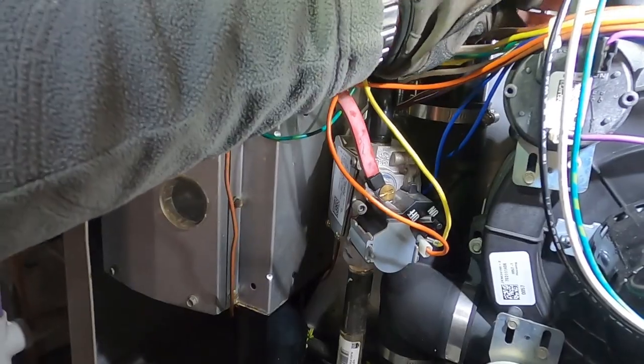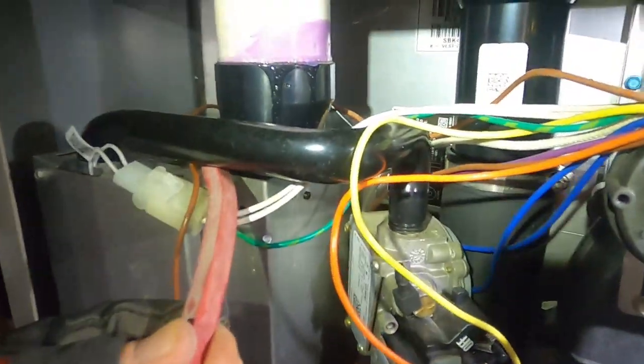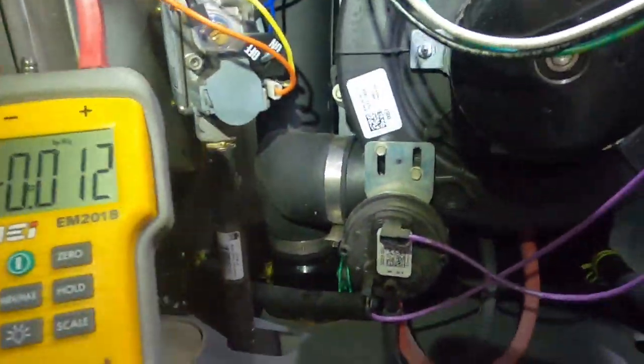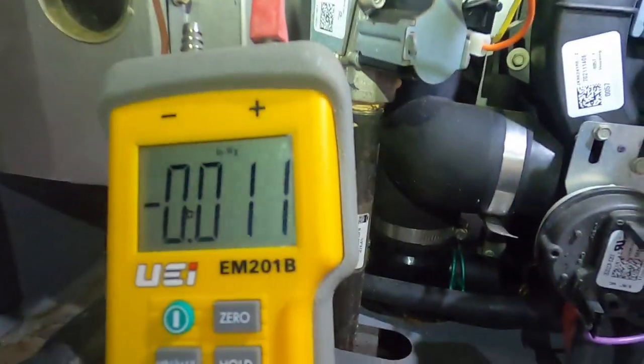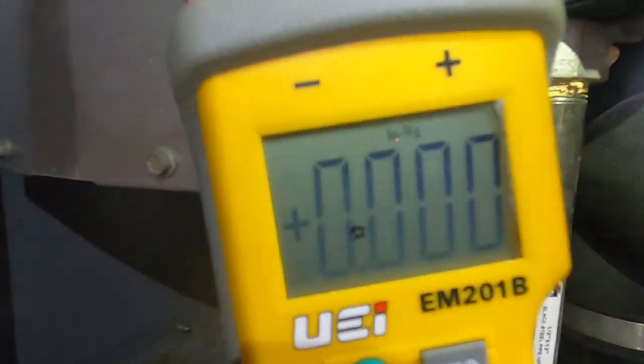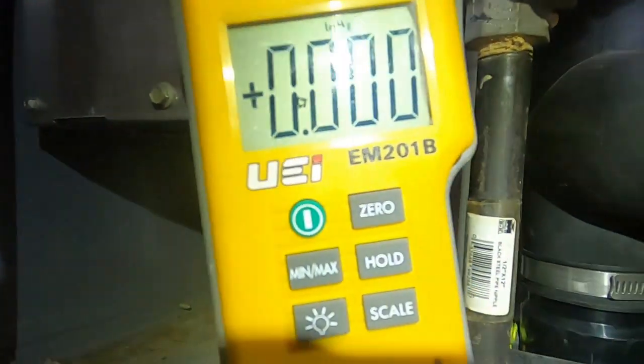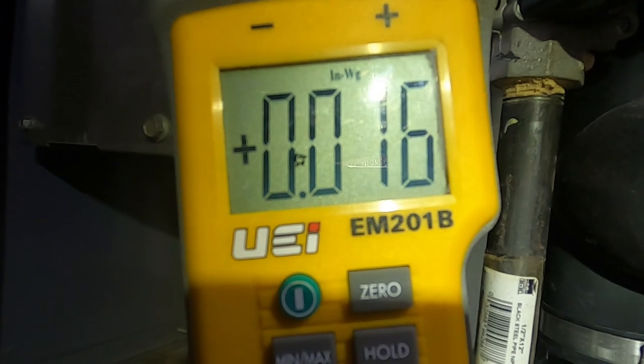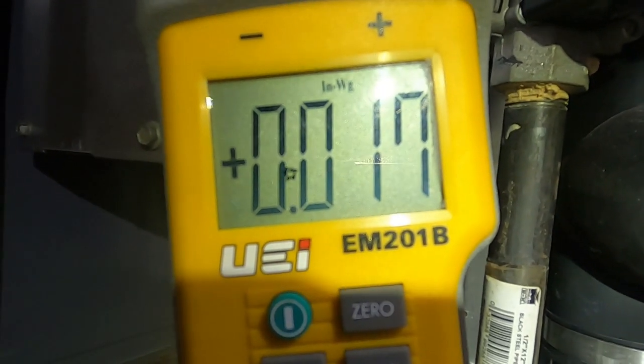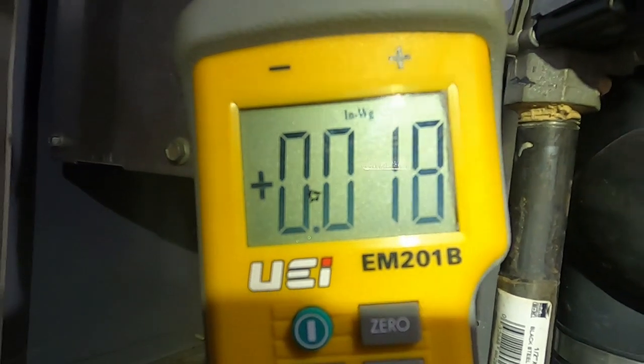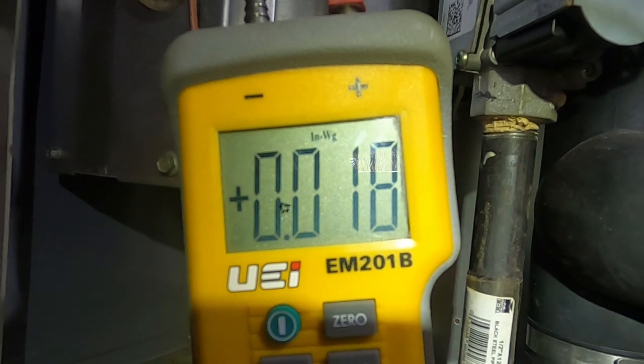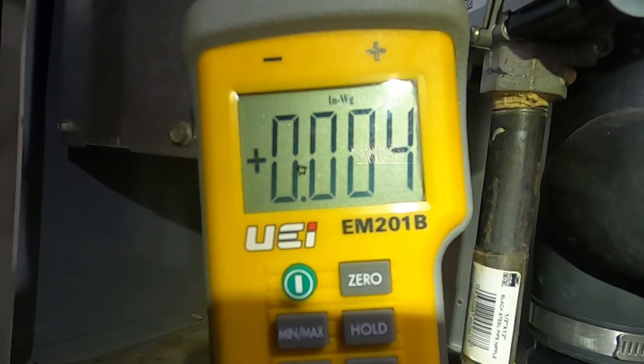And last but not least, I'm going to go over here off the gas valve from the burner box right there and see what happens there. I probably want to put my hand over that when I do it. So let's turn on the blower, cover that flue up. I'm going to take my hand off this flue real quick. And you see it dropping back down.